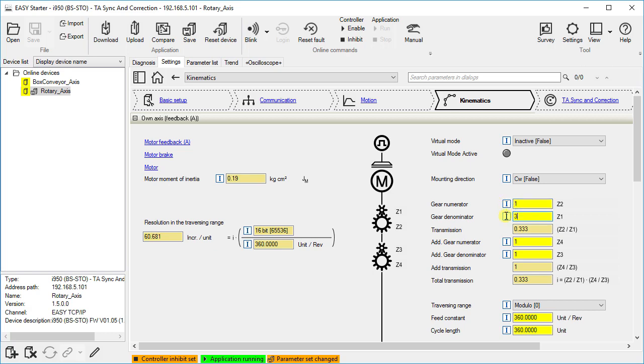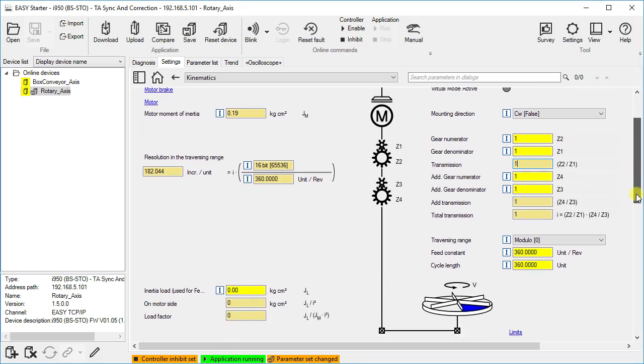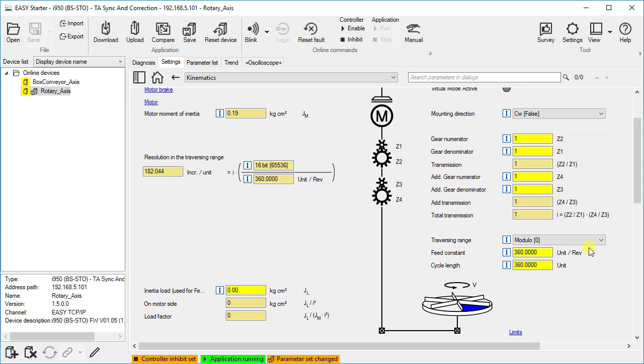We will keep the default values. Furthermore, select the traversing range via this dropdown. We will keep it to modulo in our case because our rotary axis works endlessly. The feed constant defines the distance moved with one revolution at the gear output, in our case 360 units or degrees per revolution. In the modulo system, the cycle length must also be specified to prevent an undefined numerical overflow. Here we will also keep the default values.